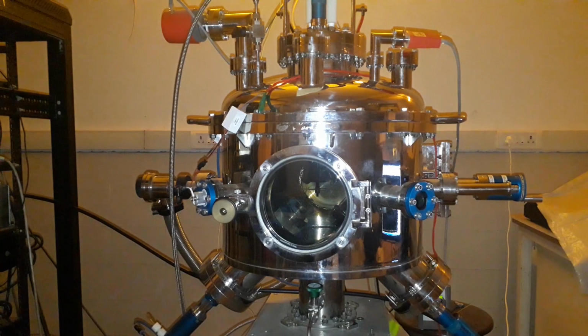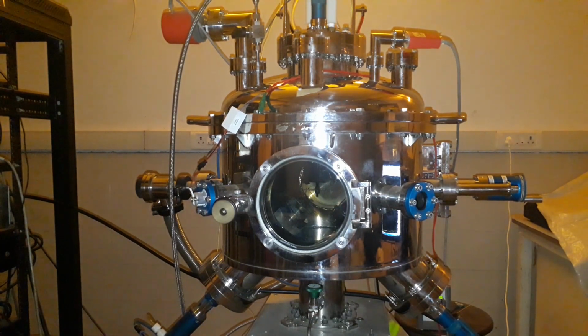There is a pressure there, and normally to start sputtering, you strike the plasma at higher pressure. It means very bad vacuum, 10 to the minus one. Because there are a lot of molecules, the plasma will strike very easily. But the problem is a lot of impurities, and you don't want that. So normally I've seen people doing it at minus three, minus two, and after that you don't get plasma, so it becomes a pain. But minus two, minus three seems like a good range for most of the evaporations.